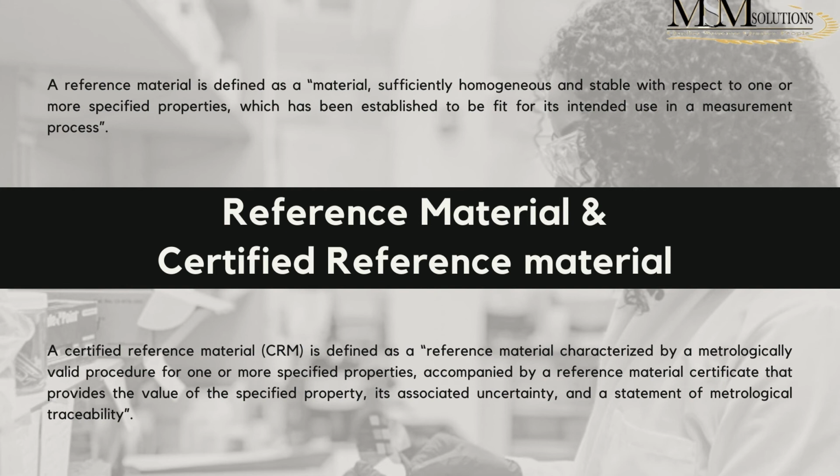We then move to defining a CRM, a certified reference material. This is defined as a reference material characterized by a metrologically valid procedure for one or more specified properties, accompanied by a reference material certificate that provides the value of that specified property, its associated uncertainty, and a statement of metrological traceability. So that is what a CRM has. It's a value of a specified property, which would be like a concentration, an associated uncertainty, and most importantly, a statement of metrological traceability.